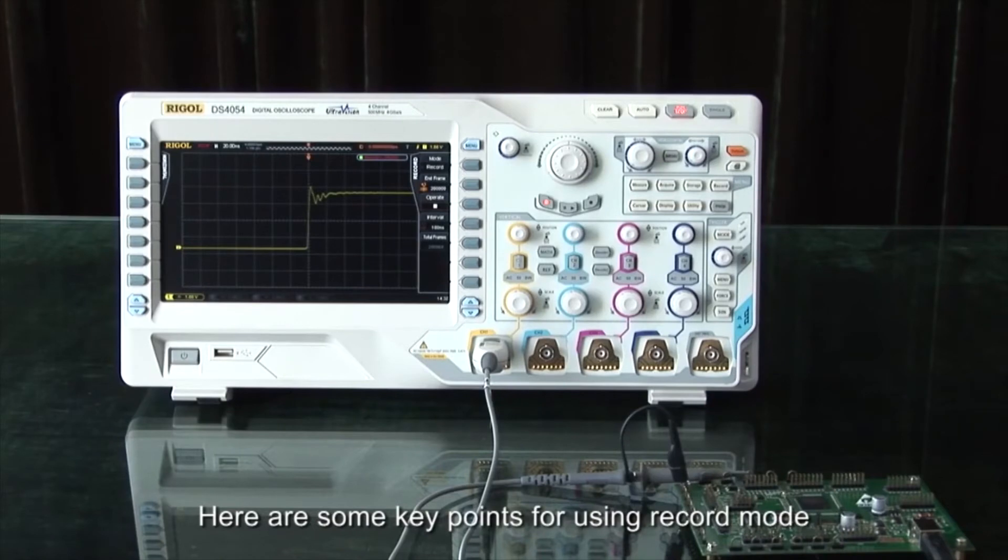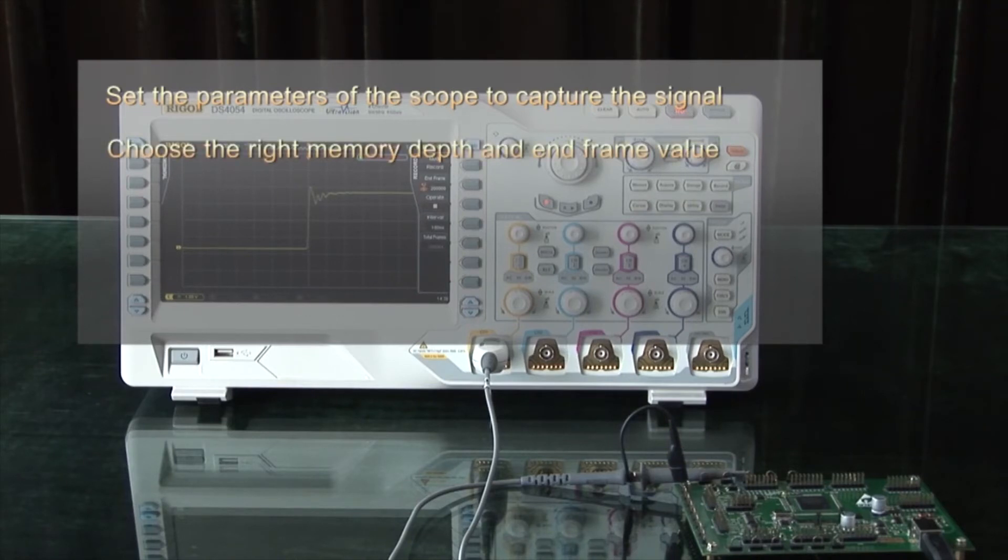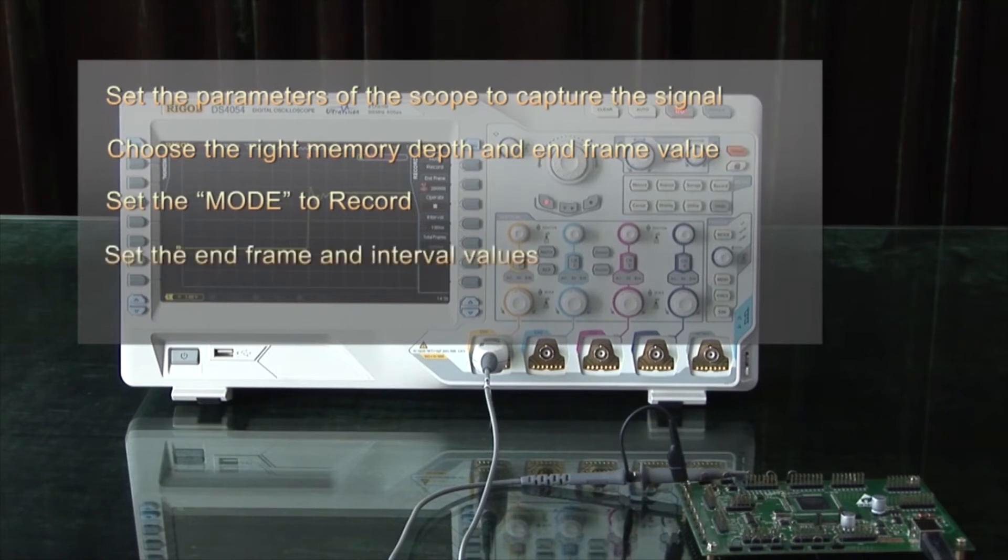Here are some key points for using record mode. You want to set some of the parameters of the scope so that you capture the signal. Choose the right memory depth and end frame value. Set the mode to record, set the end frame and interval, and then start recording.